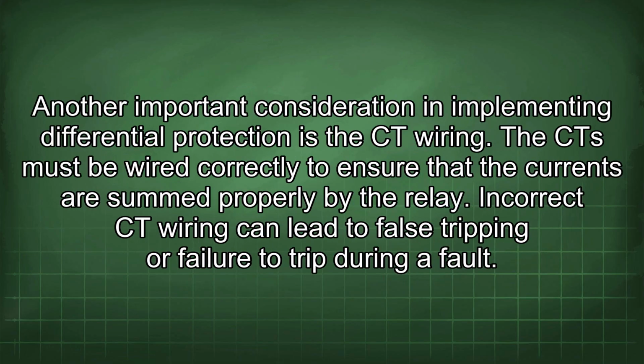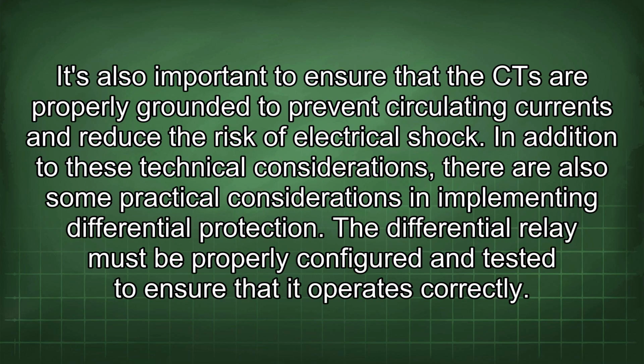Another important consideration in implementing differential protection is the CT wiring. The CTs must be wired correctly to ensure that the currents are summed properly by the relay. Incorrect CT wiring can lead to false tripping or failure to trip during a fault. It's also important to ensure that the CTs are properly grounded to prevent circulating currents and reduce the risk of electrical shock. In addition to these technical considerations, there are also some practical considerations in implementing differential protection.